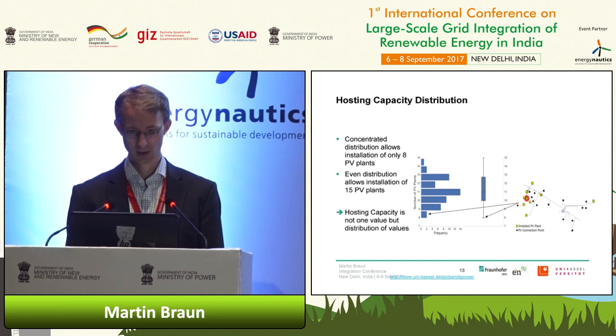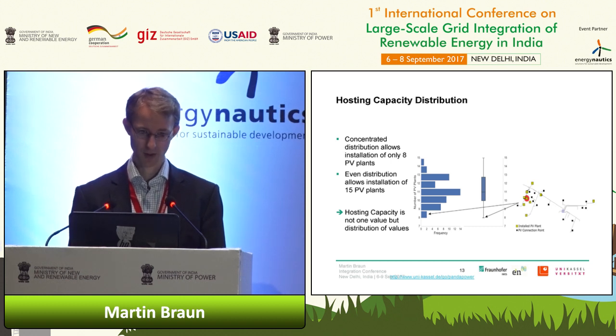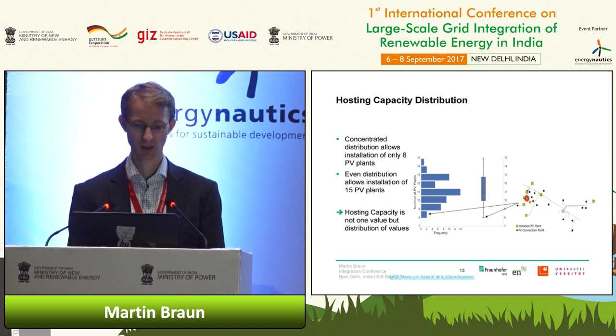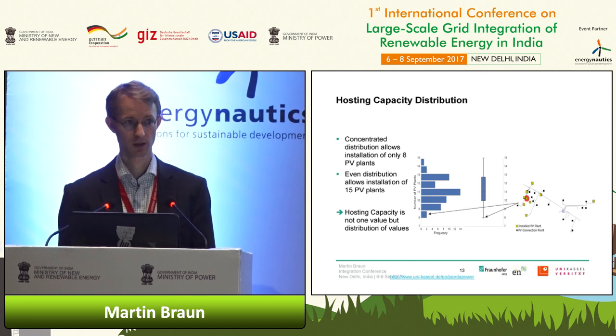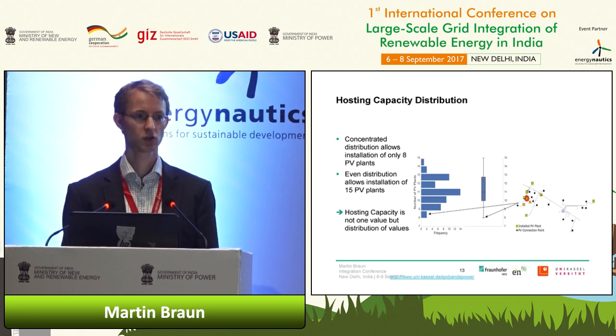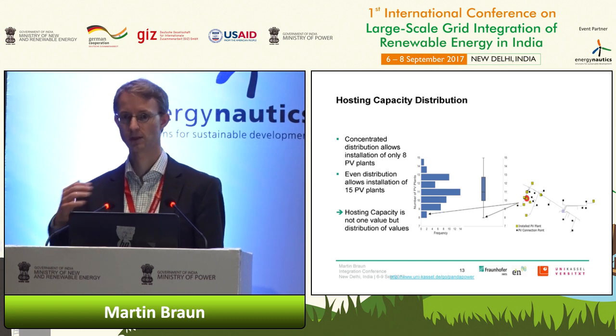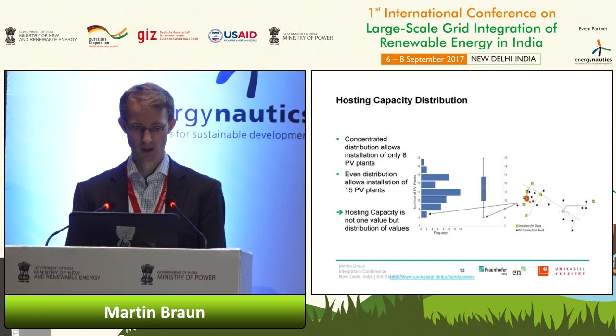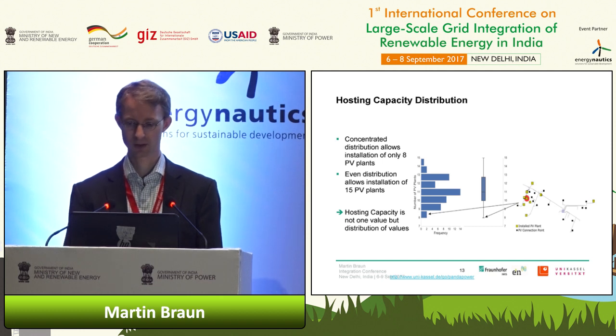If we run the analysis, depending on where the installation actually takes place, we can see there's a huge difference in how many PV plants can actually be installed, because installing near the transformer allows more hosting capacity than at the end of the feeders, which causes voltage issues. Depending on where they're installed, we get a large difference with regard to the installable number of PV plants. If you look only at one calculation, you only get one number, and this is not the reality—it could be from 8 to 15 in this little example.